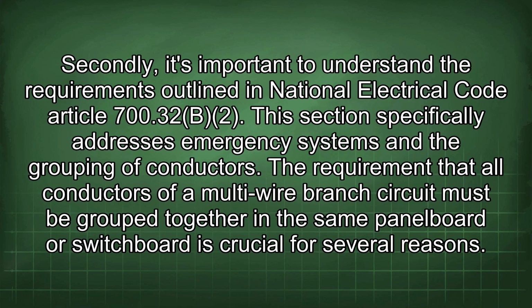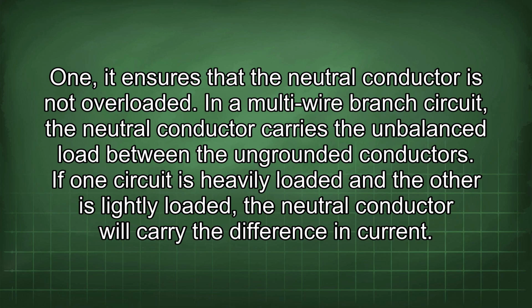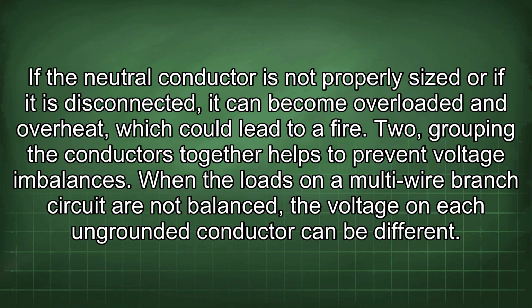Secondly, it's important to understand the requirements outlined in National Electrical Code Article 700.32(B)(2). This section specifically addresses emergency systems and the grouping of conductors. The requirement that all conductors of a multi-wire branch circuit must be grouped together in the same panel board or switchboard is crucial for several reasons. 1. It ensures that the neutral conductor is not overloaded. In a multi-wire branch circuit, the neutral conductor carries the unbalanced load between the ungrounded conductors. If one circuit is heavily loaded and the other is lightly loaded, the neutral conductor will carry the difference in current. If the neutral conductor is not properly sized or if it is disconnected, it can become overloaded and overheat, which could lead to a fire.